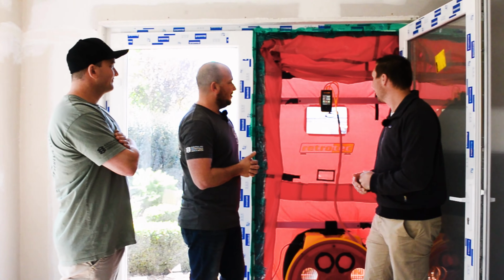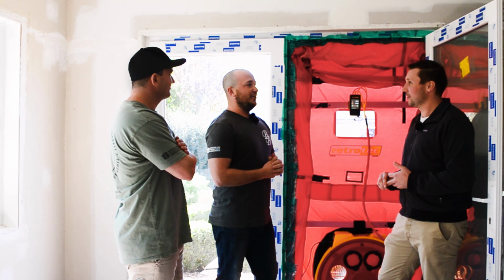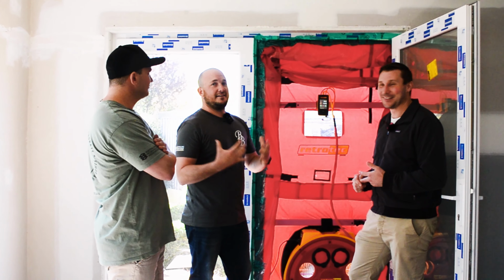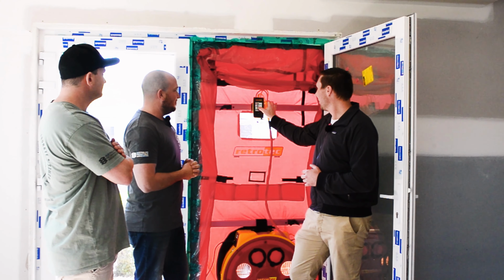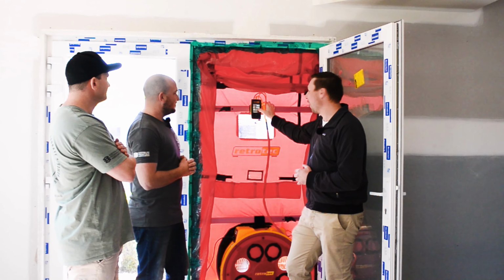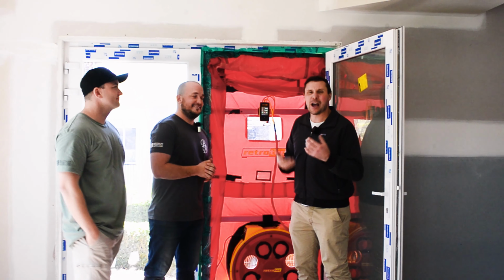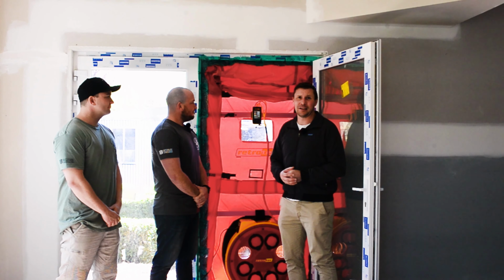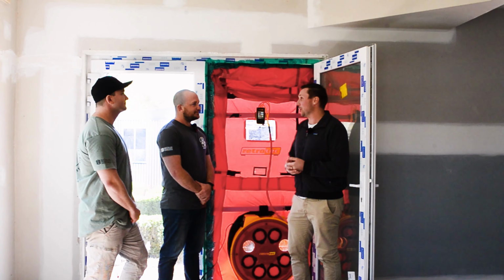Thanks, Anthony. And it's awesome to see this figure. The brief of the job was to make it more energy efficient so we didn't have our clients being cold. And well and truly, you can feel it in here. You can feel the quality of the air and more of an airtight home. So it's an exciting number to see. We're at 1.6. Great result. All right, we might walk around now and showcase some of the air leakage that we can find and how we might rectify some of that and get that number a little bit lower. But at the moment, that's sitting at a really fantastic result. And considering we've got mechanical ventilation in this project, I couldn't be happier with that.